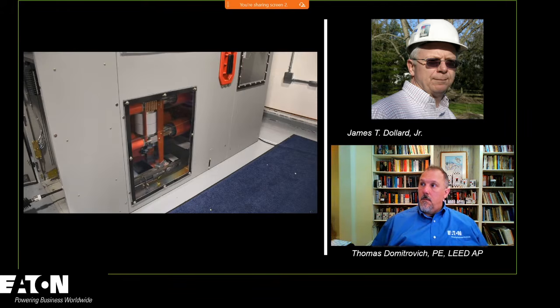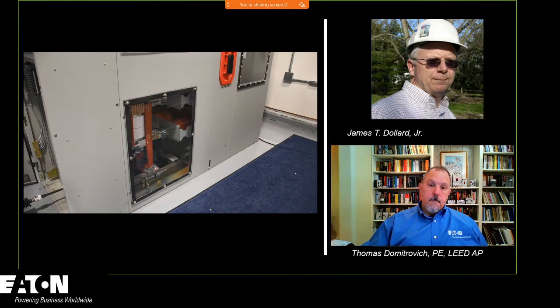And so the thing opened and it didn't blow up. So far, so good. Now you've got to rack it out. So now there's another device you set up with a little motor and a crank arm, and you get 75 feet away and rack that circuit breaker out until it comes out and is fully racked out.